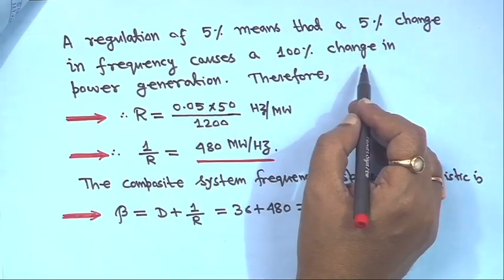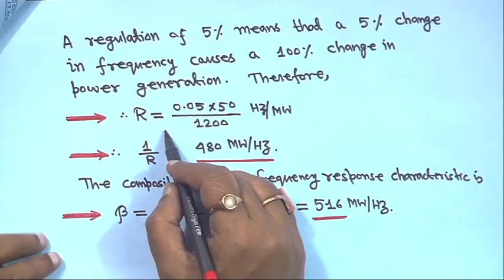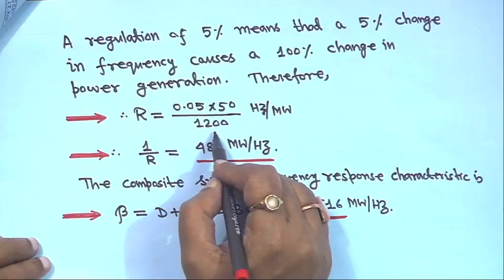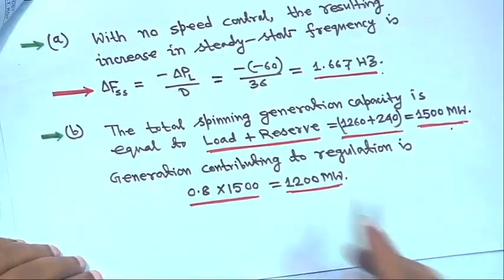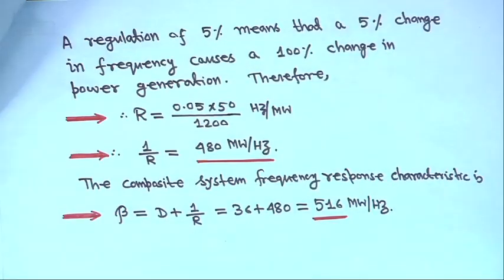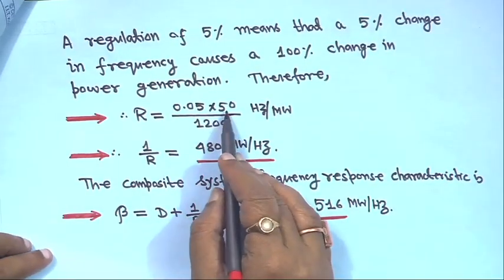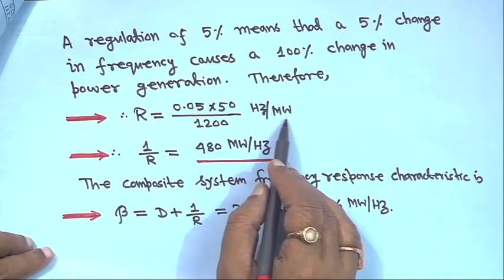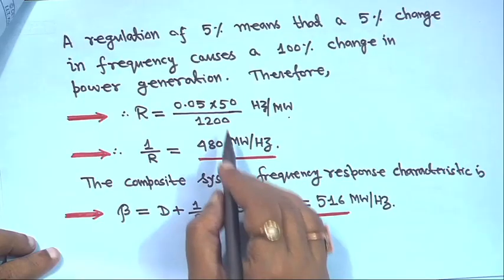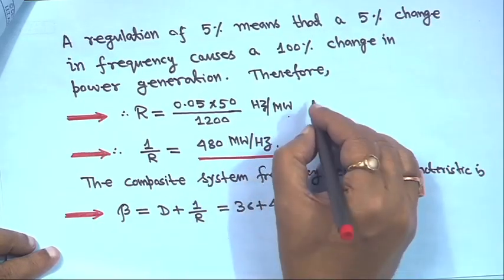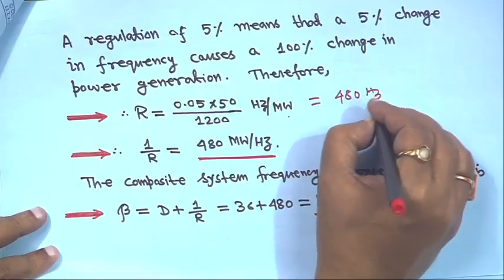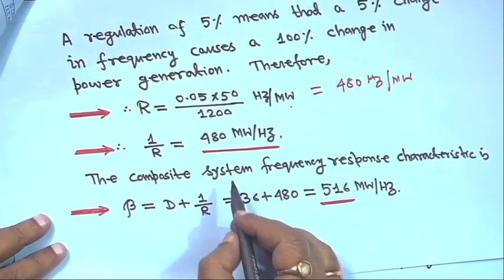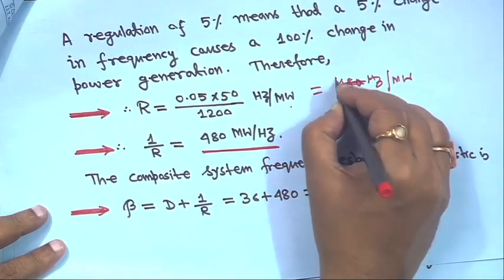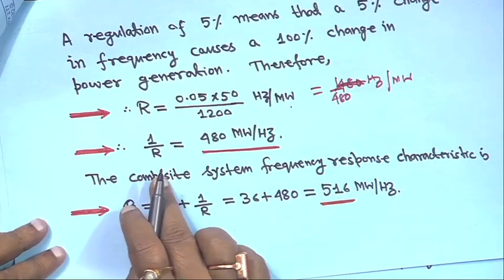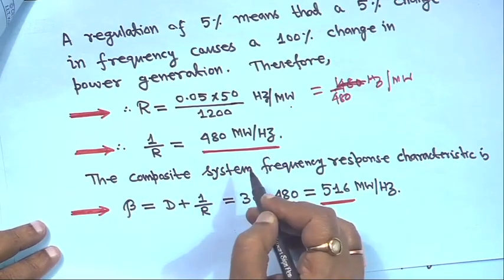Now, a regulation of 5% means that a 5% change in frequency causes 100% change in power generation. Therefore R, the regulation parameter, is 5% into 50 divided by 1200, because the generation contributing to regulation is 1200 megawatt. So R is 0.05 into 50 divided by 1200, which becomes 1 upon 480 hertz per megawatt. Therefore 1 upon R is 480 megawatt per hertz, just the reciprocal.